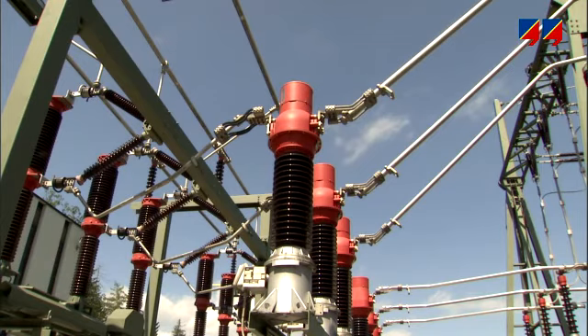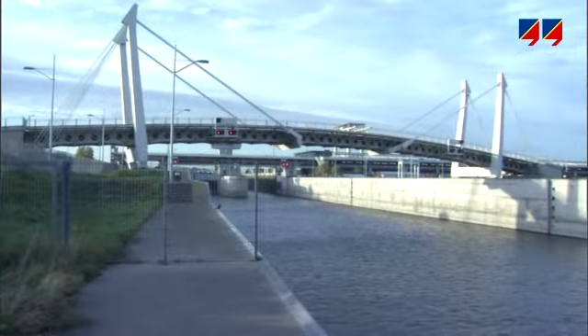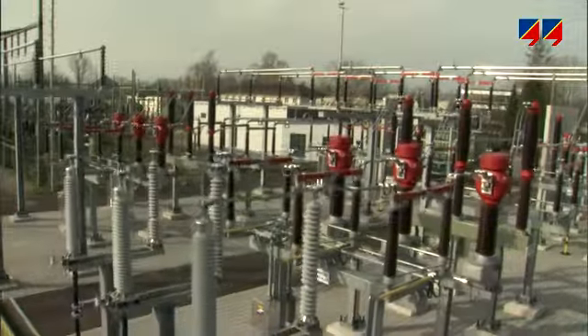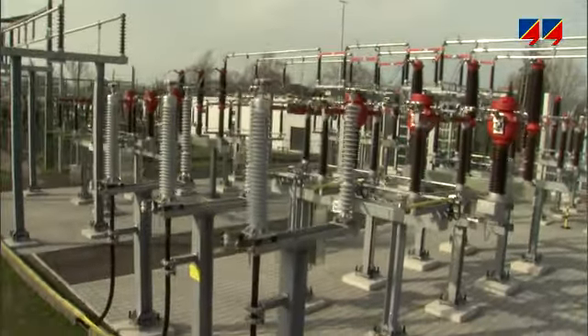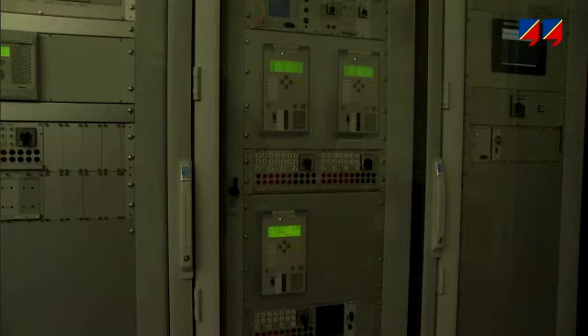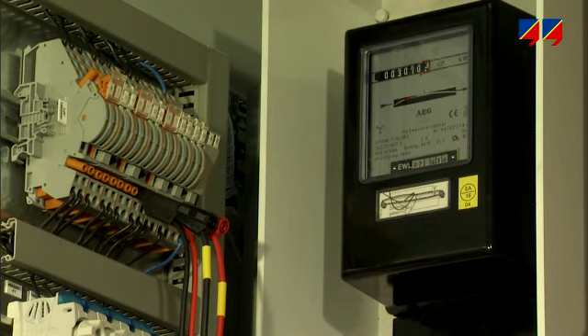Current transformers, otherwise known as CTs, are in operation 24 hours a day, 7 days a week, in power plants, substations, industrial sites, and for many other applications. Usually, they remain in use for decades. Proper specification and maintenance of the CT is important for operating protection systems safely and reliably, and for correct energy metering and billing.